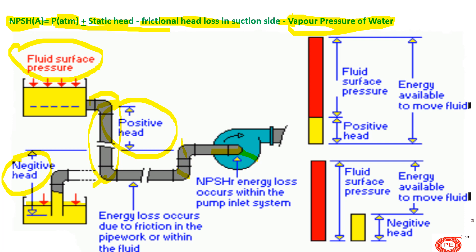Before concluding, I want to clarify the units, as many people get confused. Make sure all units are in meter water column, because most pump suppliers provide NPSHR in meter water column. P_atmosphere (1 atmosphere) equals 10 meter water column. Static head should be calculated in meter water column. Frictional head loss should also be in meter water column. Vapor pressure is in Torr, but it can be converted to meter water column by a simple multiplication factor. Ensure your units are correct so you don't calculate a wrong NPSHA.